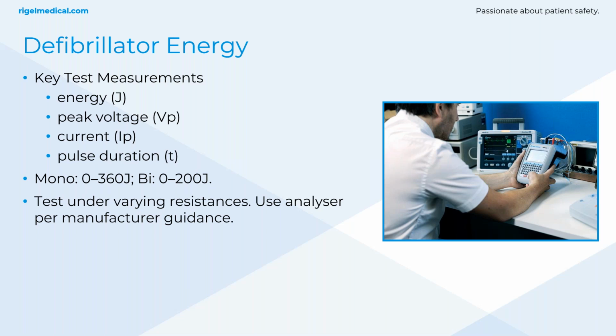and we follow those procedures. We've got peak voltage, that's just the highest voltage during the shock. Peak current, that's the highest current flowing through. The current actually gives us an insight into the strength of the electrical pulse, but it's not necessarily something that's specified in service and calibration. Then we've got the pulse duration. This tells us how long the energy is being delivered.